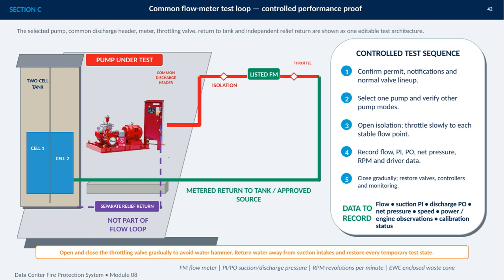The test sequence begins by confirming permits, notifications, and the normal valve lineup. I then select one pump for testing and verify the operating modes of the other pump. The isolation valve is opened, and the throttling valve is adjusted slowly to establish each stable flow point. At every point, I record flow, suction and discharge pressures, net pressure, speed, driver observations, and calibration status. Finally, I close the system gradually, restore the valves, controllers, and monitoring, and return every temporary test condition to normal.